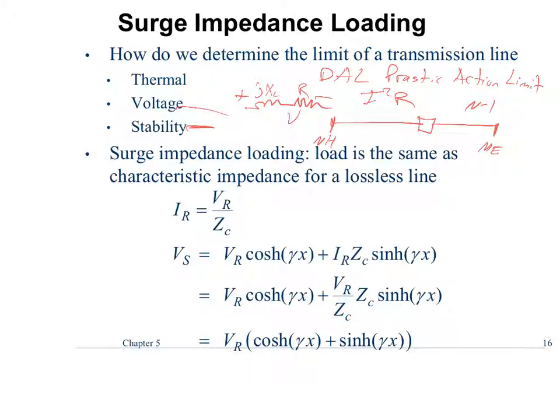N-1 is a NERC mandate that says the absolute worst case piece of equipment removed from your system. I don't care what it is, the absolute worst case. In New England, it's usually the DC line that comes down from Canada, because it's got, you know, any point in time about 10% of the power. If that trips offline, what should the system be? Still stable. Still better be stable. Well, it's got to be able to pick up the slack of the worst component in the system. Right, so if you're moving 2,000 megawatts through that line, or if you got Maine Yankee, or not Maine Yankee, Millstone trips offline, any of those things that happen, the system needs to be able to be stable after that fact. That's called N-1 contingency. You lose the worst case piece of equipment, the system still is stable. It's not in a great place, but it's still a stable system.